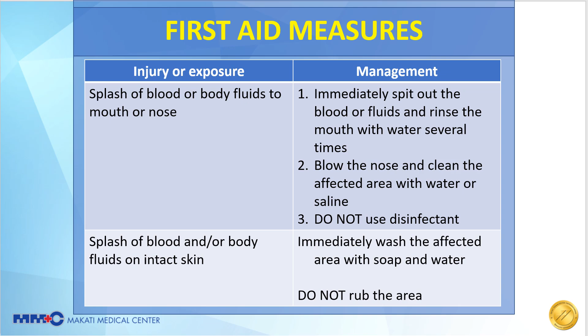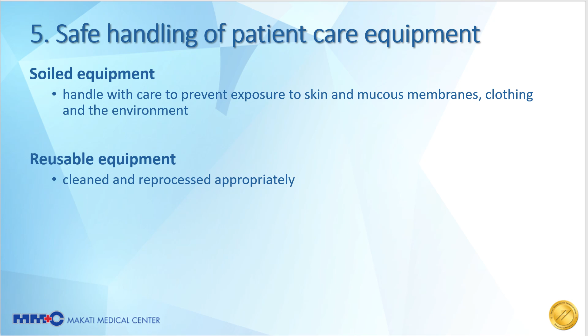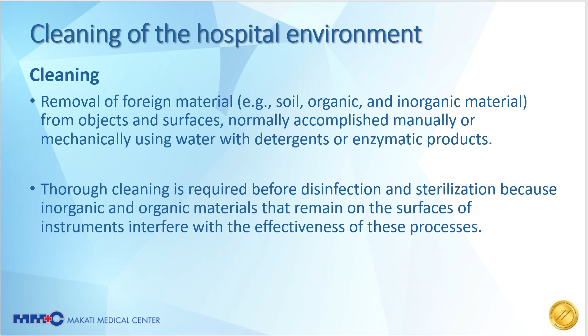Soiled equipment must be handled with care to prevent exposure to skin and mucous membranes, clothing, and the environment. Reusable equipment must be cleaned and reprocessed appropriately. Cleaning involves removal of foreign material from objects and surfaces, normally accomplished manually or mechanically using water with detergents or enzymatic products. Thorough cleaning is required before disinfection and sterilization because inorganic and organic materials that remain on the surfaces of instruments interfere with the effectiveness of these processes.